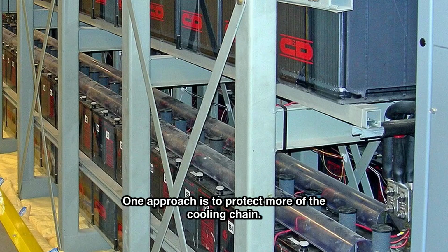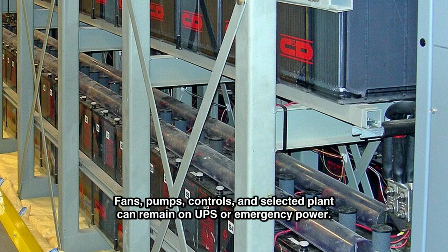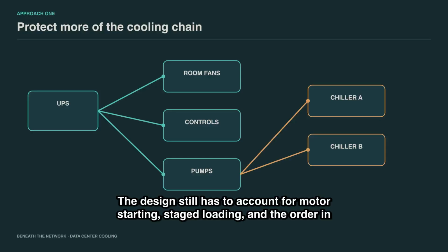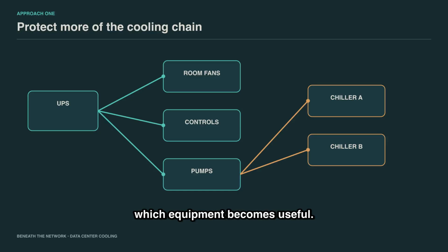One approach is to protect more of the cooling chain. Fans, pumps, controls, and selected plant can remain on UPS or emergency power. The design still has to account for motor starting, staged loading, and the order in which equipment becomes useful.